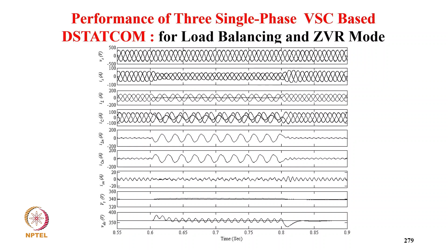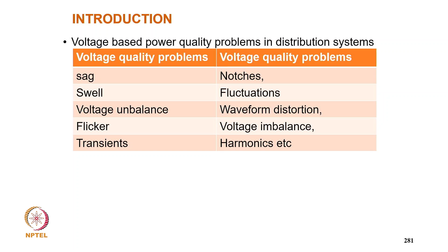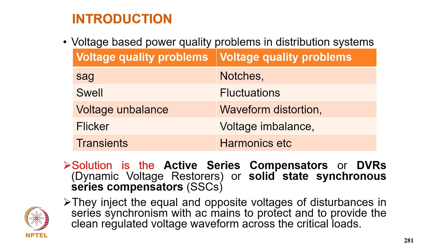Now coming to the solution to power quality problems: active series compensation for voltage-based problems. The voltage-based power quality problems in distribution systems are voltage sag, voltage swell, voltage unbalance, voltage spikes, voltage notches, voltage fluctuation, waveform distortion, and harmonics. The solution is the active series compensator, dynamic voltage restorer, or solid state series compensator. They inject a voltage equal and opposite to the disturbance in series, synchronous with the AC mains, to protect and provide a clean regulated voltage waveform across the critical load.